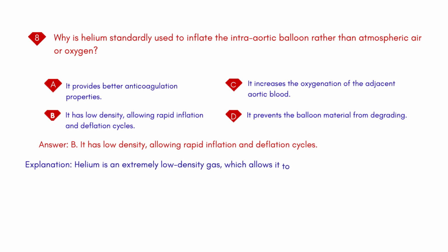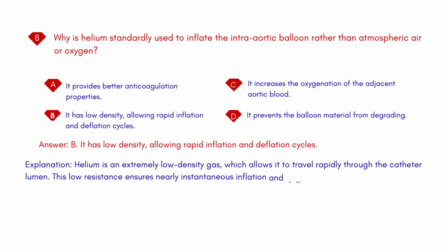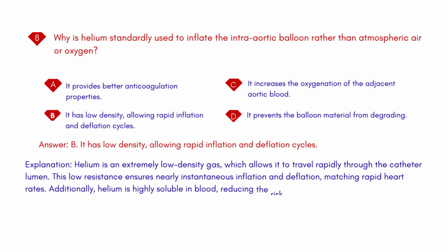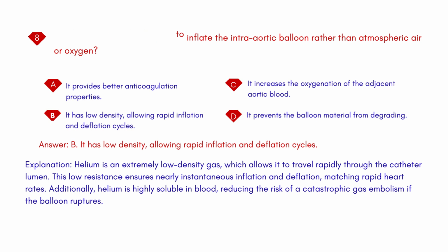Explanation: helium is an extremely low-density gas, which allows it to travel rapidly through the catheter lumen. This low resistance ensures nearly instantaneous inflation and deflation, matching rapid heart rates. Additionally, helium is highly soluble in blood, reducing the risk of a catastrophic gas embolism if the balloon ruptures.